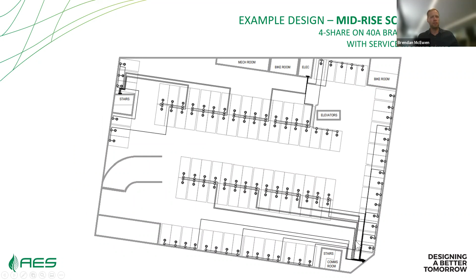And this is an example of what the costing looks like. We've got the transformer and EV distribution board breakers here, so you have to install this equipment to be able to provide power for your EV charging. We've got a whole range of equipment feeding panel boards and then branch circuits out to each parking space. We've also got communication systems, which make up a not negligible component of the cost, 27,000 out of a total incremental cost here of 194,000.